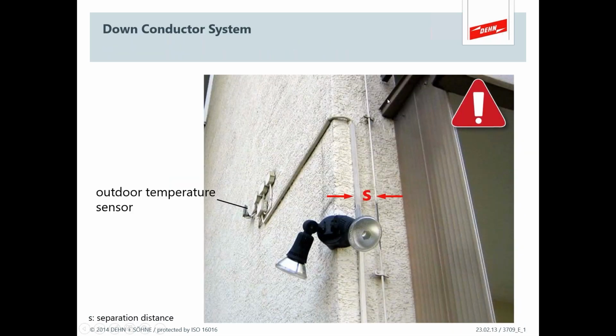Now we'll talk about the down conductor system, and right away you see the points. Separation to other electrical systems that you want to keep away from your lightning path. And so selecting your down conductor is a great idea and having it run the side of the building, but you can see a couple of mistakes. This might be a metal flange. If that's a metal flange and it's within flashover distance, the NFPA code calls that bonding distance, and the IEC standards call that separation distance. I use separation line. It's essentially the same thing.